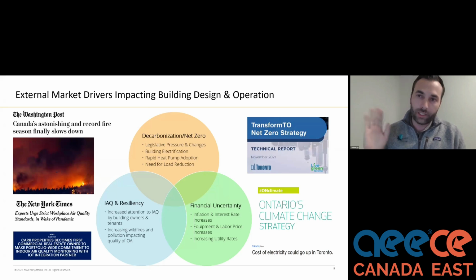How many times have you walked into an existing building and you just know those outside air dampers are turned off? Well, if there's source control going on in that building, if you have a device or devices removing the volatile organic compounds that we've traditionally tried to dilute, well, then that building has increased resiliency for the future.